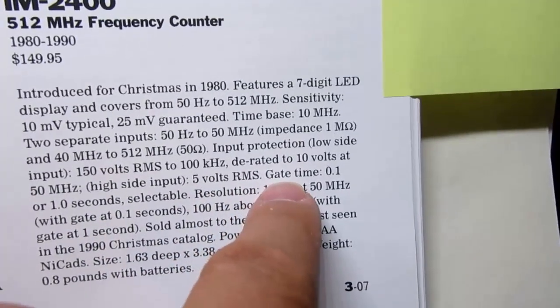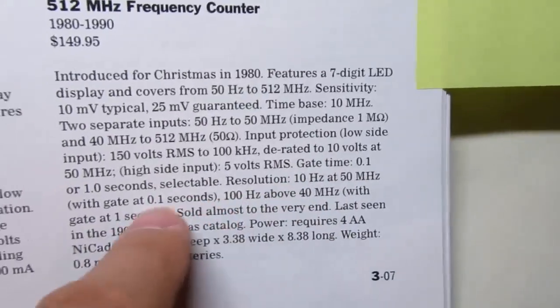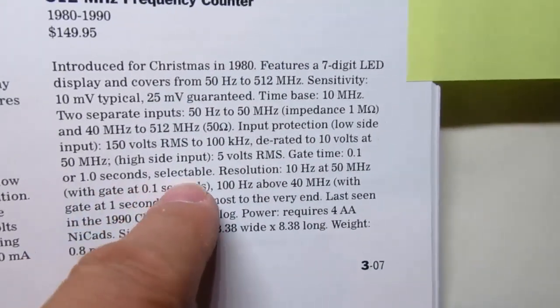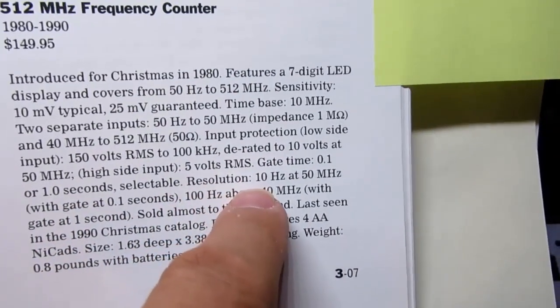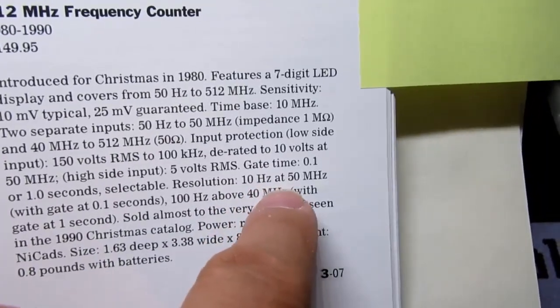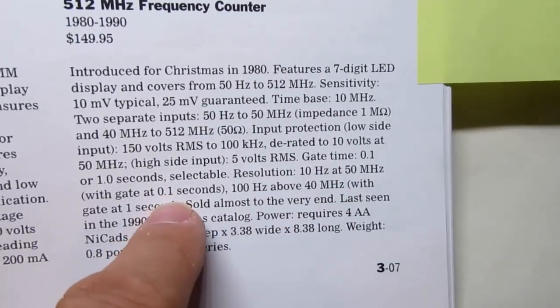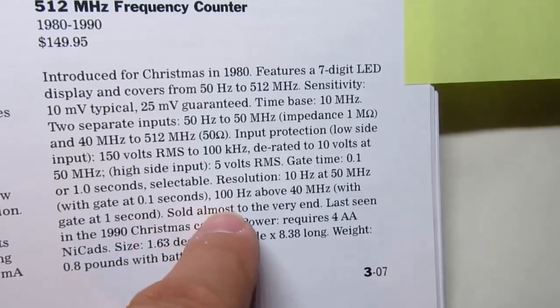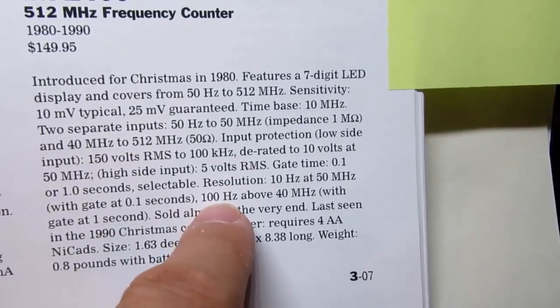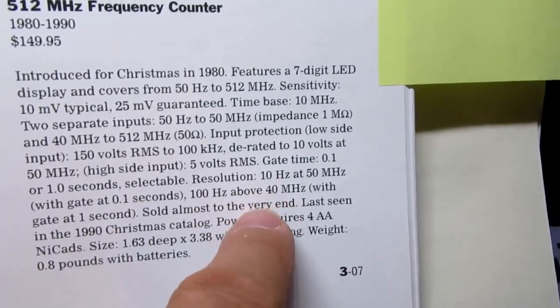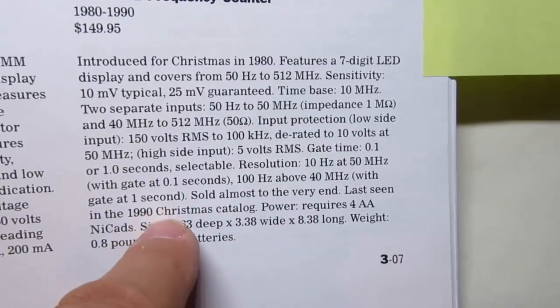It has a selectable gate time of 0.1 seconds or 1 second. It has a resolution of 10 hertz on the 50 megahertz range, assuming you're using a gate time of 0.1 seconds, or a resolution of 100 hertz above 40 megahertz with a gate set at 1 second.